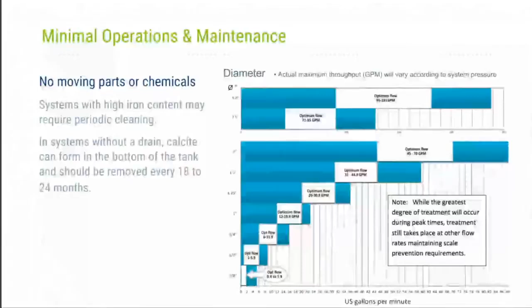What we noticed after the baseline period, when we put in this system, is that the temperature within the water started to rise. If you think about the equation Q equals UA delta T, the heating element was still trying to put the same amount of heat into the system, but because the thermal resistance, the calcite, wasn't there anymore, the element stayed cooler, it didn't burn up, and the water temperature warmed up. It warmed up to the point where the operations staff had to go adjust the thermostat and take it down to a medium setting. And you can see the point on the graph where that was accomplished. Next slide, please.